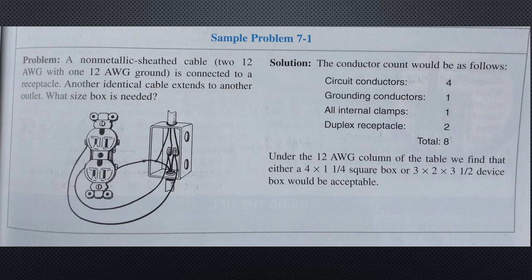Moving on to sample problem 7-1, the first one of the chapter. The problem is: a non-metallic sheathed cable, two 12 AWG with one 12 AWG ground is connected to a receptacle. Another identical cable extends to another outlet. What size box is needed? The solution for the problem: the conductor count would be as follows. Circuit conductors, in this case four. Grounding conductors, one. All internal clamps are counted as one. And finally, the duplex receptacle is counted as two, for a total of eight. So under the 12 AWG column of the table, that is Table 314.16 A, we find that either a four by one and a quarter square box or a three by two by three and a half device box would be acceptable.